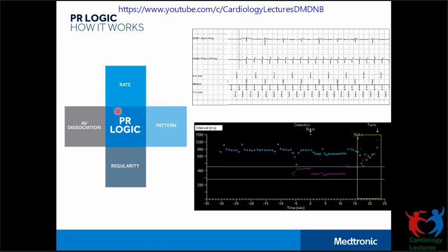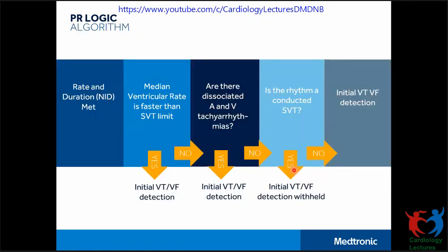PR Logic works on four criteria: it looks at rate, the pattern of A and V, the regularity of ventricular intervals, and AV dissociation. In this example, the RV Tip to RV Ring EGM shows ventricular rates higher compared to the atrial EGM, suggesting a possible ventricular tachyarrhythmia. Also, looking at the onset of this rhythm, it occurs quite abruptly. Upon meeting the rate criteria and NID, it checks the median ventricular rate relative to the SVT limit.